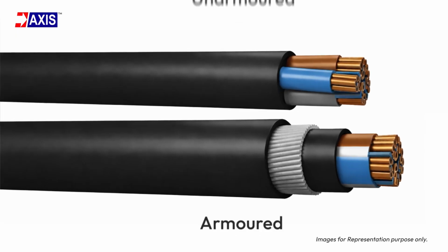Each cable type has a different construction. The insulation, screen and outer sheath all change based on the cable type. Because of this, the components inside the termination kit will also change. Also check whether the cable is armored or unarmored. Armored cables include an additional metallic layer for mechanical protection. In this case, the termination kit must include provisions for earthing the armor and rebuilding the outer sheath. If you ignore this, the cable will not be properly grounded and will become unsafe. Unarmored cables do not require this step, so the termination design is simpler.